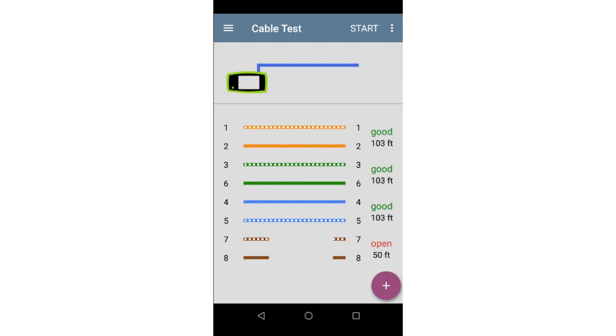Here we can see that pair 7-8 is open at 50 feet, while the other pairs are over 100 feet in length. This would indicate that pair 7-8 has been cut or was never connected at a cross connect.